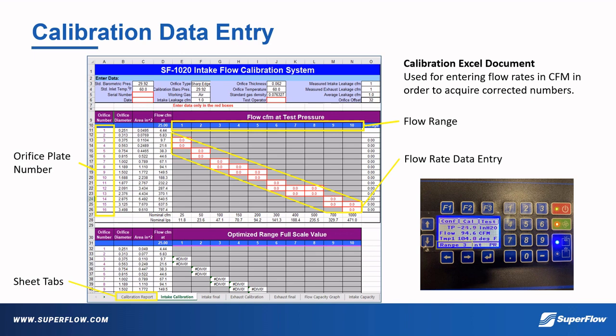The flowcom panel on the right shows that a range of 3 is selected. The flowcom also shows a stabilizing pressure of 25 inches H2O and is flowing at a rate of 94.6 CFM. Comparing this with the expected numbers of the Excel document, we can see that this is close to how the bench is expected to perform.